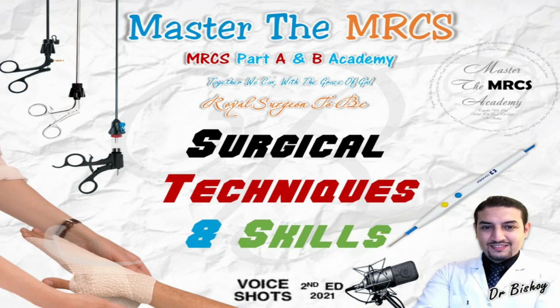So we are all now familiar that electrosurgery is a term to describe roughly the diathermy modes. Electrosurgery utilizes the heat generated by the passage of a high frequency alternating electrical current through the living tissue. The application of the voltage across the human tissue results in the formation of an electrical circuit between the voltage source and the tissue. The tissue acts as a resistor, and the level of resistance is determined by the water content of the tissue, and this is the whole trick. It is the resistance that results in the formation of the heat.